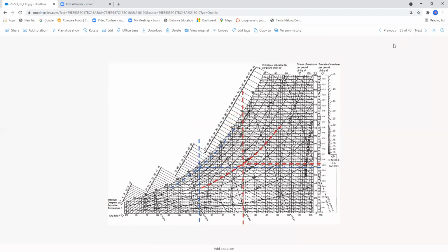Here we have a figure found on page 1067. This is the supply and return conditions on a psychrometric chart. The absolute humidity drops as a result of the reduced moisture content of the cool supply airstream. So what are we saying? If you know how to read this diagram and plot your air conditioning system, in a perfect world this thing should remove moisture from the air as it is removing heat at the same time. The result is we have a very comfortable supply air temperature and low humidity.